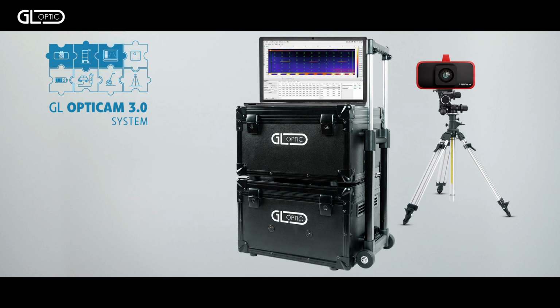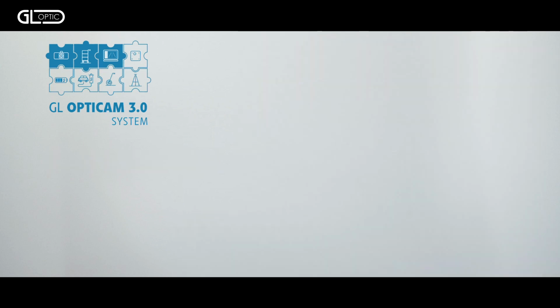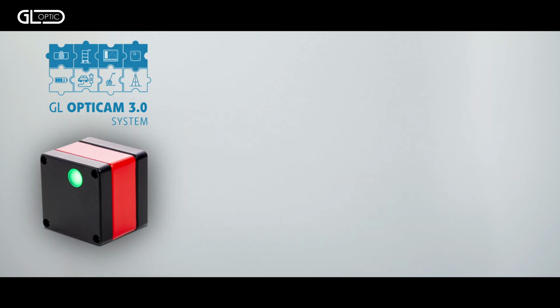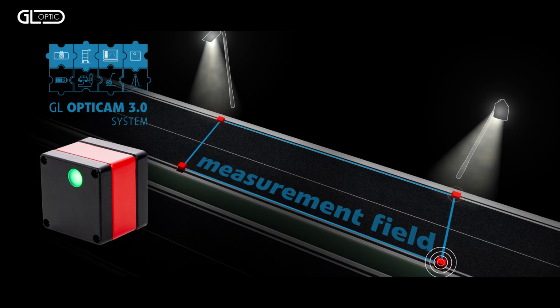There is room for a dedicated computer equipped with specialized software, GL Opticam Soft. Thanks to this, immediately after taking a picture, you can determine whether the lighting meets the requirements of the standard. An indispensable part of the kit are active measurement field markers used to mark the measured part of the road. This allows the measurement grid to be quickly applied in the software so that the analysis goes very efficiently.